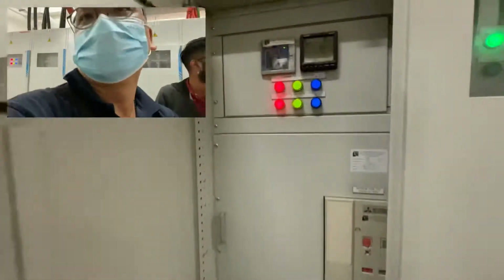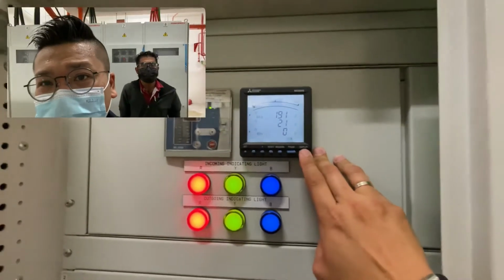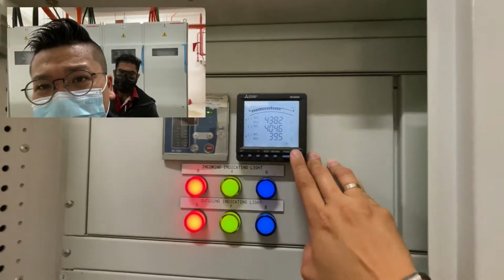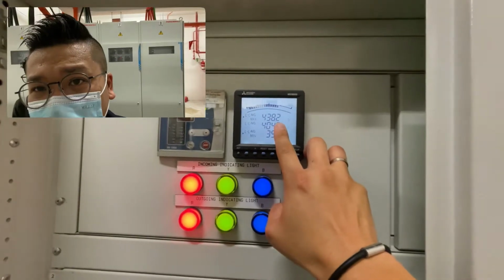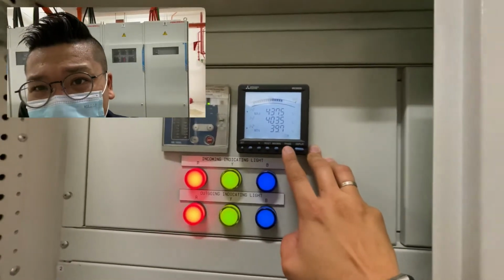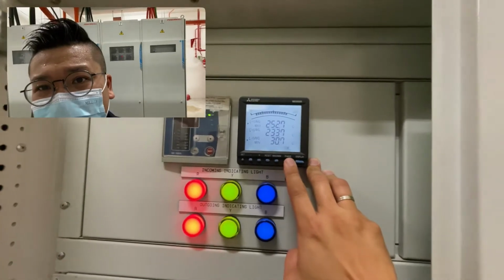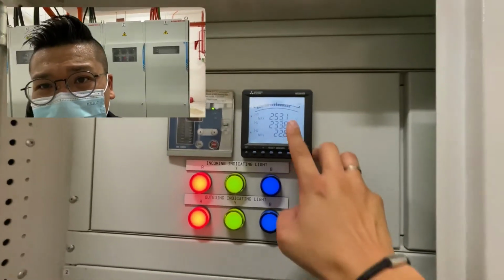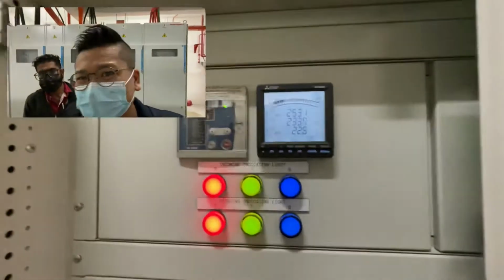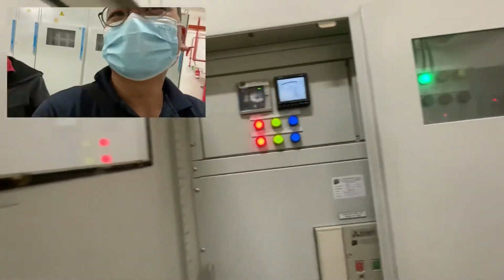This is MSB 1 coupler, and then we have the incoming. This is incomer 2 from transformer number 2. This is a 3-phase, this is average, this is on the high side. A little bit higher on the high side. This is a voltage 253, slightly a little bit higher, 253. Some cases I see before about 260 volt. So what is the normal one? Normal under average about 240.